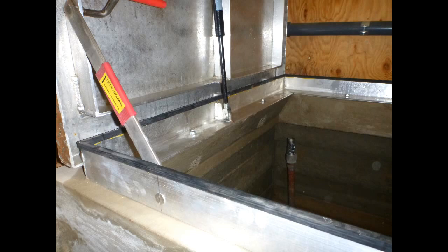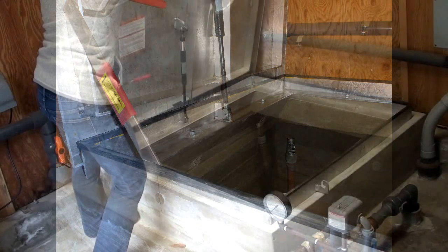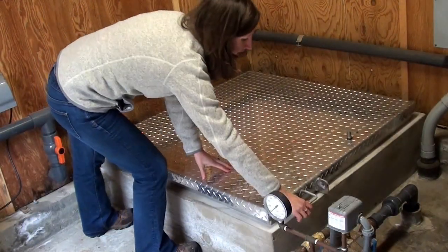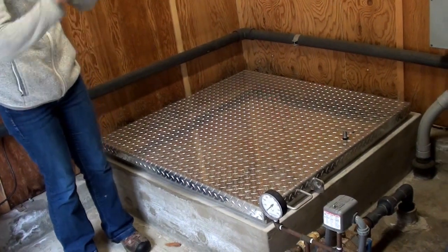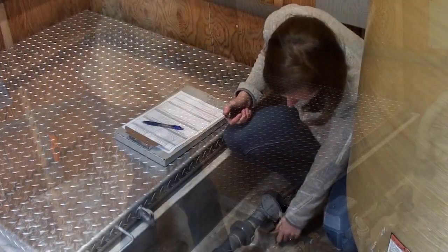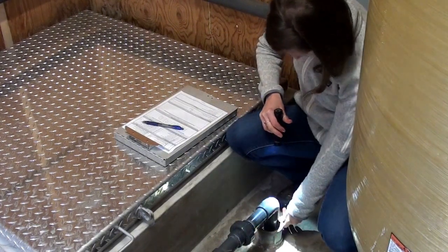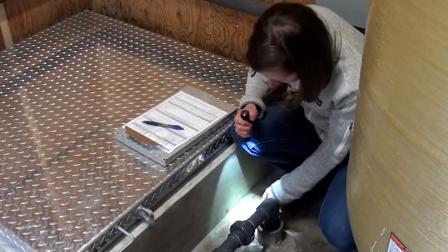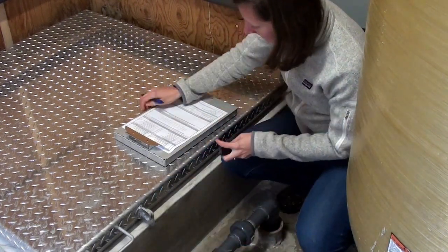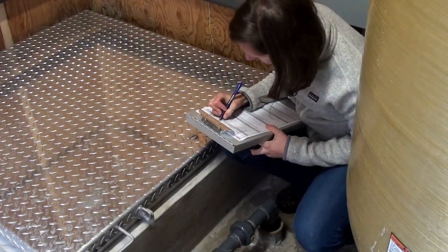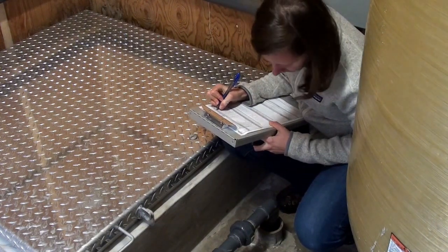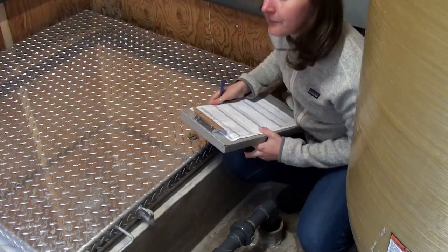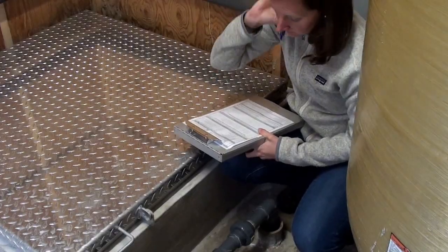Take a good look at storage tank access hatches. Make sure that the hatch is watertight with a good seal and gasket, and that the lid latches securely. Make sure any penetrations for pumps, level controls, or chemical addition points are constructed in a way to keep surface or rainwater, insects, and rodents out of the tank. In the example shown, the penetration where the pump supply line goes into the tank is not sealed. The void around this pipe could allow contamination to easily enter the tank.